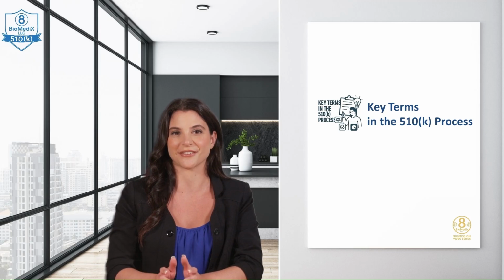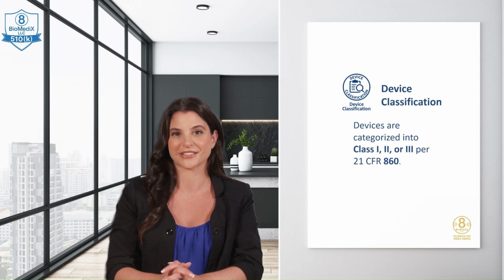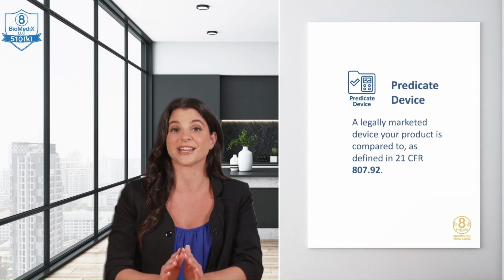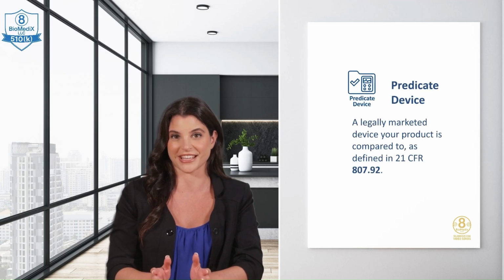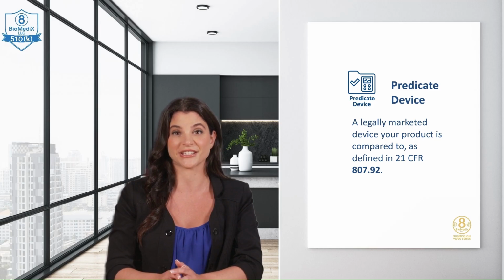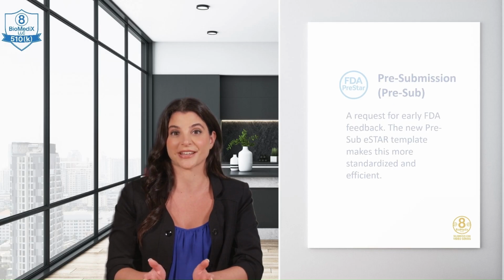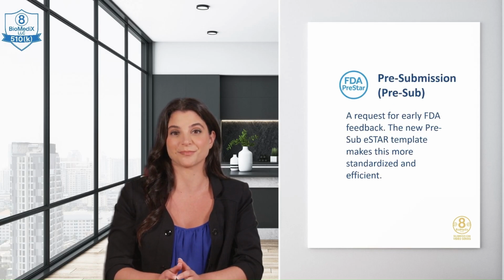Key terms in the 510(k) process. Let's wrap up this section by reviewing some key terms you'll see throughout the 510(k) process. Device classification. Devices are categorized into Class 1, 2, or 3 per 21 CFR 860. Predicate device. A legally marketed device your product is compared to, as defined in 21 CFR 807.92. Pre-submission, pre-sub, a request for early FDA feedback. The new pre-sub eSTAR template makes this more standardized and efficient.